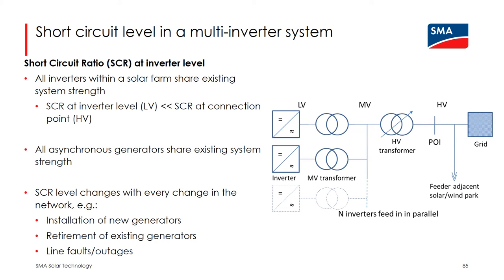And what's so unique about the Australian market? I think everybody here knows that one of the main aspects is that typically those projects are connected to a network which provides only a low short circuit level. The most commonly used term is actually short circuit ratio. Short circuit ratio gives you an idea on the size of the generator installed at a certain point of interconnection in the network in comparison to the short circuit power the network does provide.